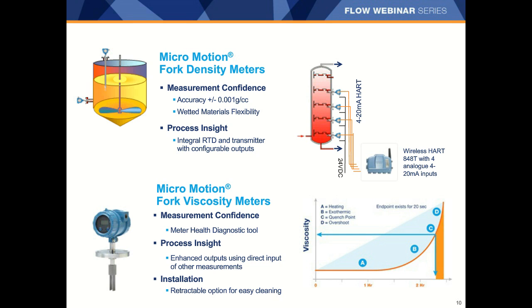Some of the benefits you could realize from our density fork is reliable measurement even in aggressive acid, alkali, and slurry applications with multiple wetted material options. Increased reliability of product interface detection with a highly accurate process measurement. Improved operator safety by reducing hazardous liquid exposure risks through use of an inline device where no manual sampling is required. And you can get enhanced readings like dynamic, kinematic, and referred viscosities and densities from a single device by using the external inputs of temperature, pressures, or flow measurements.